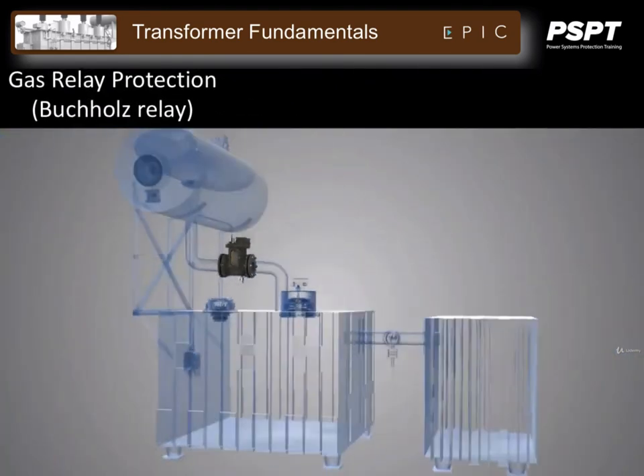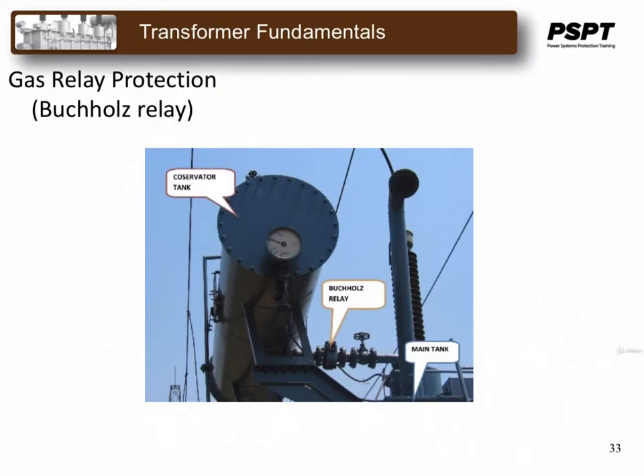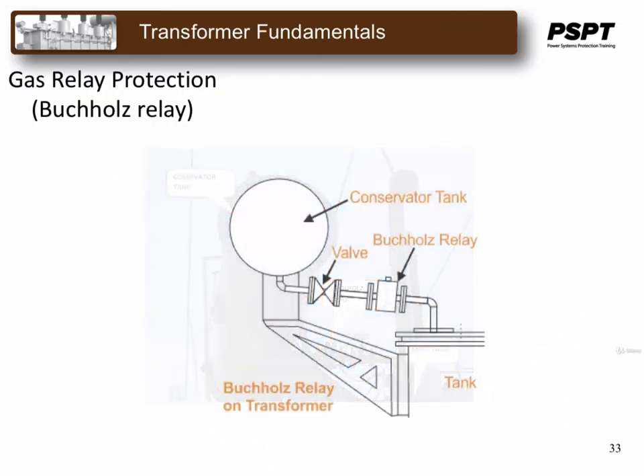The Buchholz relay is located in the oil line that connects the conservator tank and the main transformer body. This position of the relay above the main tank will accumulate any and all gases that are formed and rise in the transformer. Also, any pressure surges that occur will pass through the oil connection line on the way to the conservator tank.